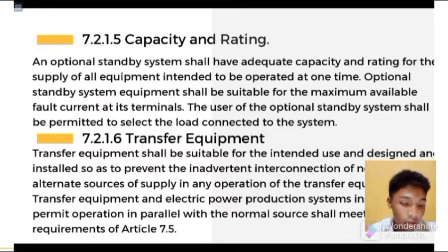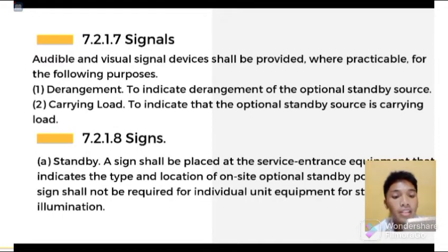Transfer equipment located on the load side of the branch circuit protection shall be permitted to contain supplementary overcurrent protection having an interrupting rating sufficient for the available fault current that the generator can deliver. For the signals, audible and visual signal devices shall be provided where practicable for the following purposes. There are two purposes. First, for derangements, to indicate derangement of the optional standby source. Number 2, carrying load, to indicate that the optional standby source is carrying load.